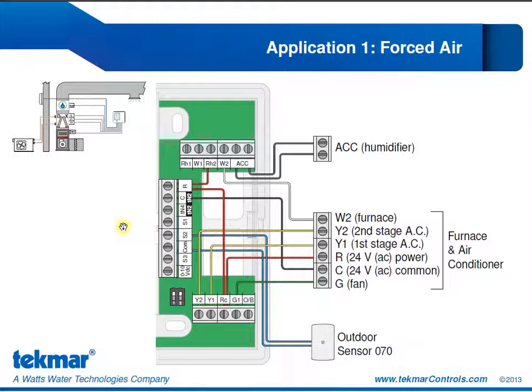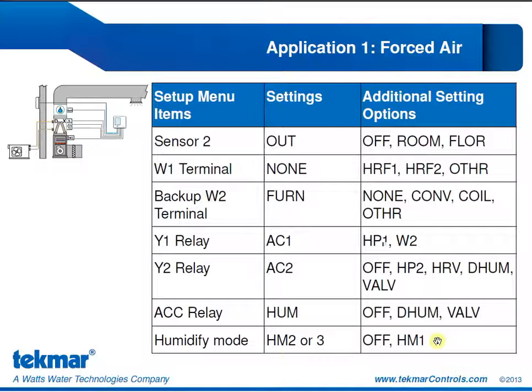We've also connected an outdoor sensor to the sensor 2 terminal. An outdoor sensor is not necessary for this operation, something that would likely be desired by the residents. We've shown it on the mechanical, so we're showing it on the wiring diagram.